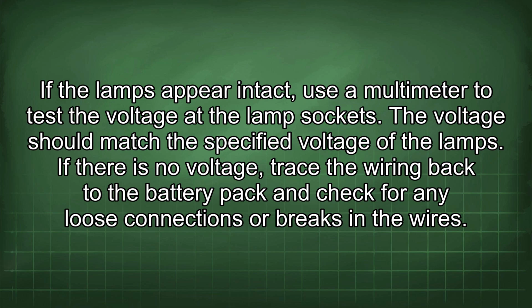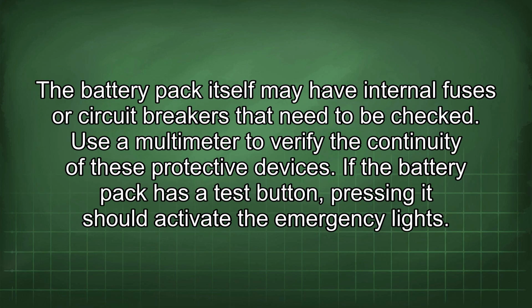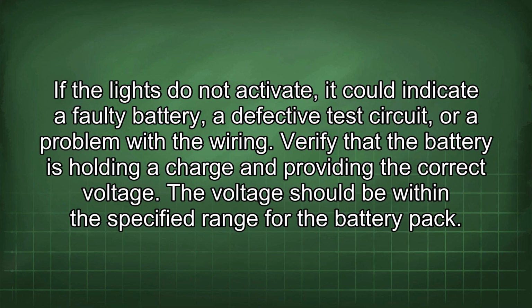If there is no voltage, trace the wiring back to the battery pack and check for any loose connections or breaks in the wires. The battery pack itself may have internal fuses or circuit breakers that need to be checked. Use a multimeter to verify the continuity of these protective devices. If the battery pack has a test button, pressing it should activate the emergency lights. If the lights do not activate, it could indicate a faulty battery, a defective test circuit, or a problem with the wiring. Verify that the battery is holding a charge and providing the correct voltage.